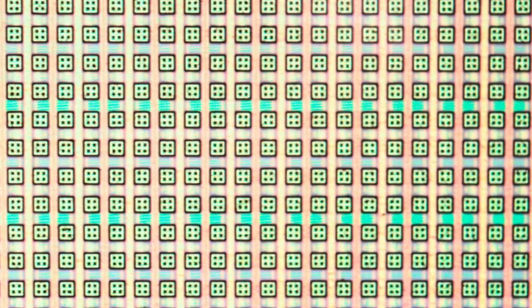The entire system resides on a single complementary metal oxide semiconductor integrated circuit that has been thinned to just 50 micrometers and occupies less than 1/1000th the volume of a standard implant. With a total size of about 3 cubic millimeters, the flexible chip can curve to match the brain's surface perfectly. This tiny device contains an astounding 65,536 electrodes, 1,024 recording channels, and 16,384 stimulation channels.